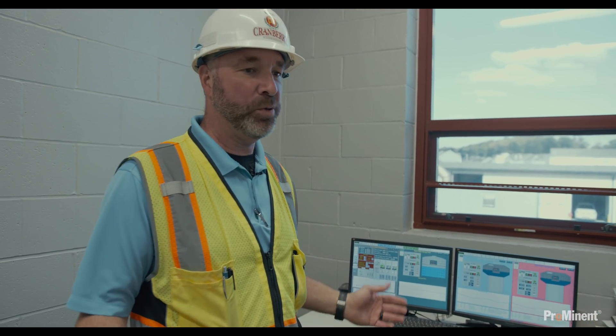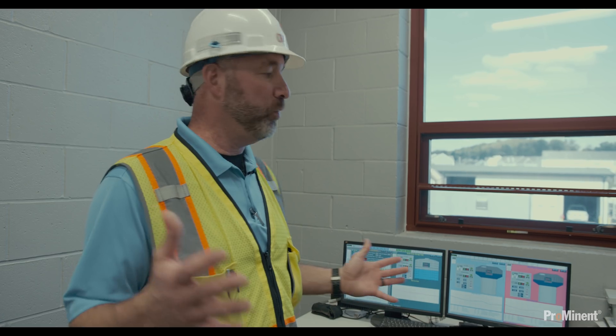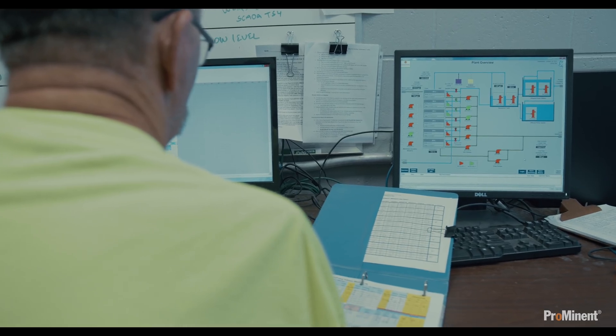We are in our operations control center looking at our computer systems. We have two systems, both called SCADA — Supervisory Control and Data Acquisition. That software and computer network allows us to look at remote field sensors, pump run statuses, and brings data back to the operator's control center. We can monitor and trend our dissolved oxygen levels, monitor how often a pump turns on and off. It's a very powerful tool for operators to operate, diagnose, troubleshoot equipment, and fine-tune the wastewater treatment process.